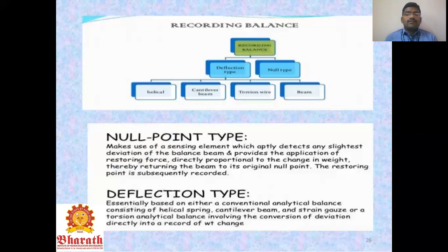The null point type makes use of a sensing element which detects any slight deviation of the balance beam, and applies a restoring force directly proportional to the change in weight, thereby returning the beam to its original null point. The restoring force is subsequently recorded. The deflection type is essentially based on either a conventional analytical balance consisting of a helical spring and cantilever beam, or a strain gauge and torsion balance, involving the conversion of the deviation directly into the recorded weight changes.